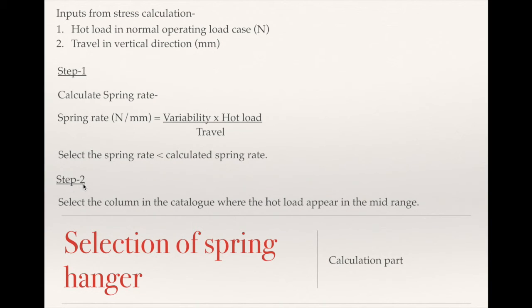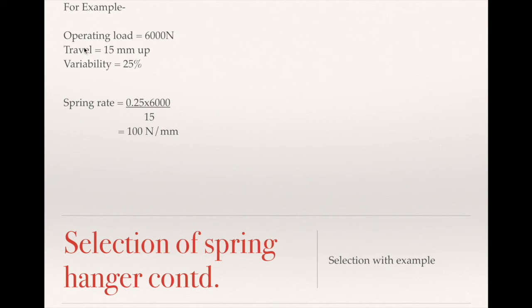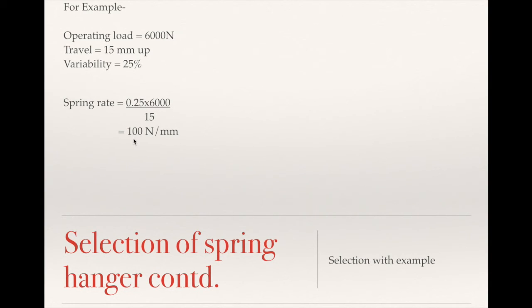Step 2 is to select the column in the catalog where the hot load appears in the mid-range. For example: operating load from stress calculation is 6 kN (6000 N), travel is 15 mm up, and variability is 25%. Calculating the spring rate: 0.25 × 6000 ÷ 15 = 100 N/mm. So the calculated spring rate is 100 N/mm.